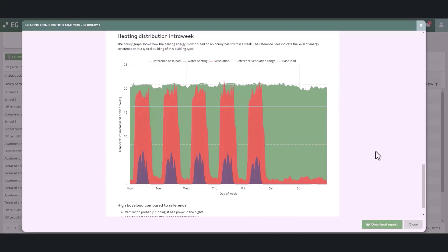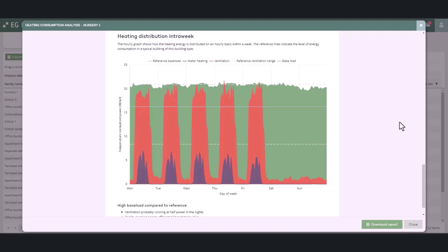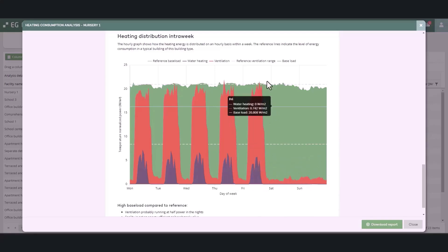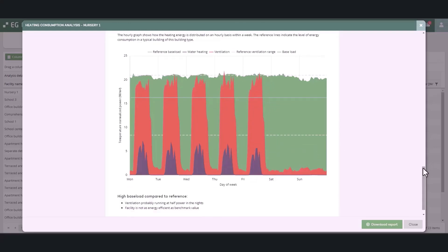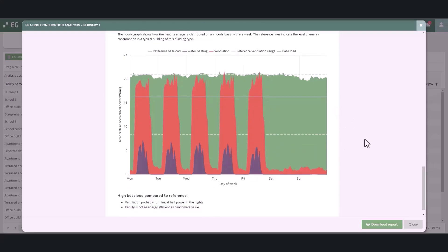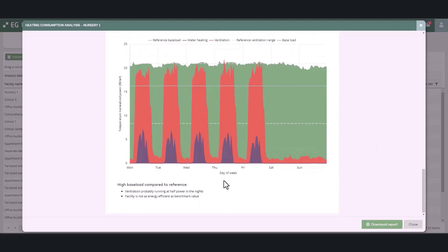High ventilation heat consumption could indicate that the heat recovery of ventilation is poor, air volume is higher than normal, or the temperature of ventilation air is unnecessarily high. You can also see how the power levels of the ventilation vary on business days and weekends. High base load compared to reference can be a sign of ventilation running on partial power constantly, or that the building's insulation is not as good as on average in similar buildings.